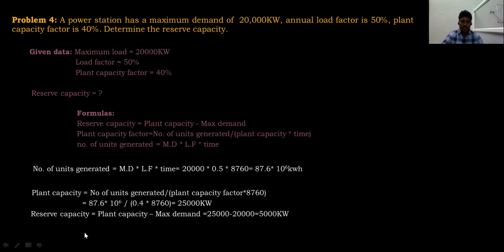Here reserve capacity is equal to plant capacity minus maximum demand, as I already told you. Plant capacity is 25,000 kilowatts and maximum demand is 20,000. So the plant has the capacity to generate 25,000 kilowatts, but it is operating at a maximum load of 20,000. So we have a reserve of 5,000 kilowatts. That is called the reserve capacity of a power plant.